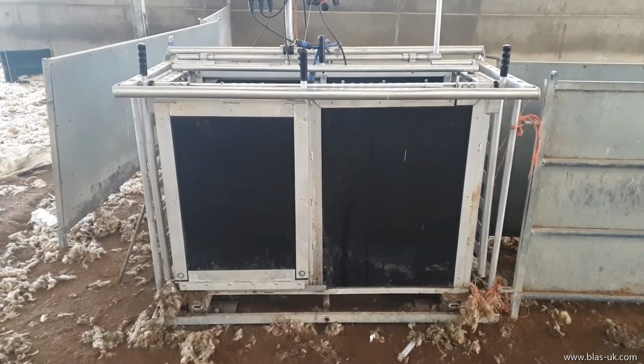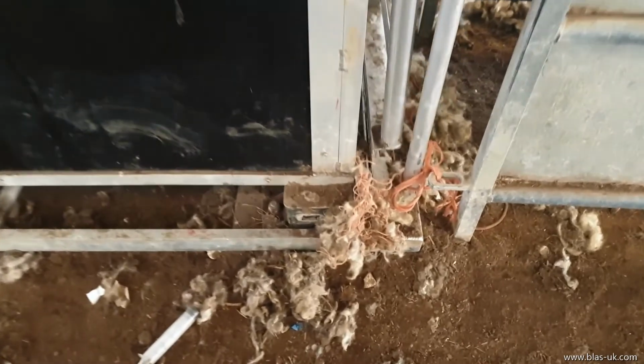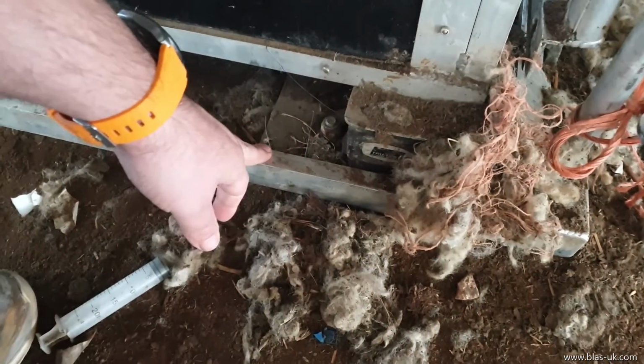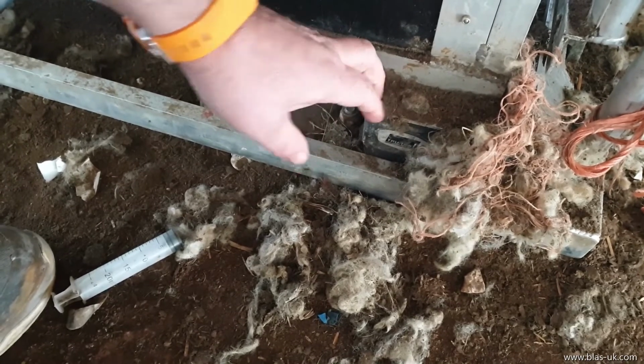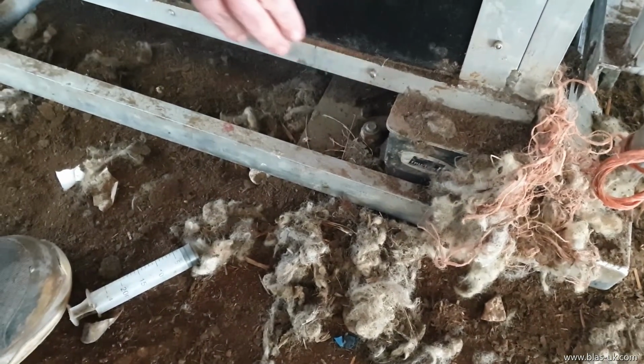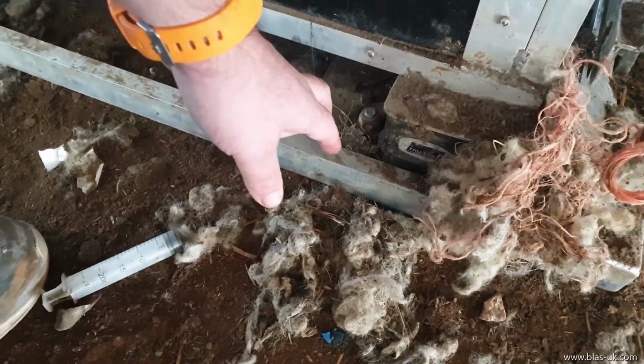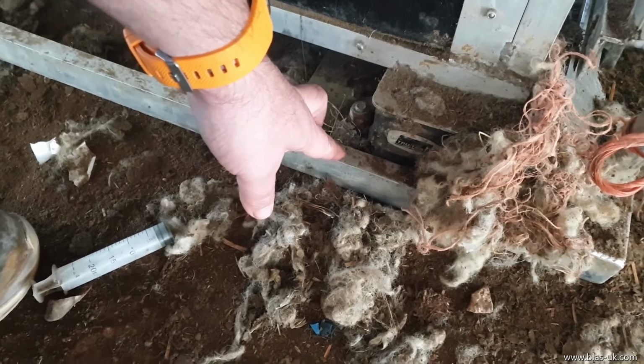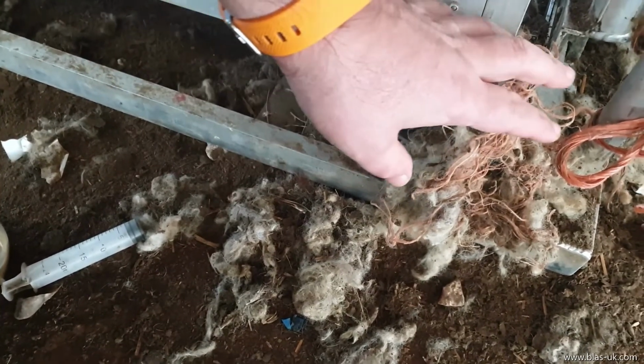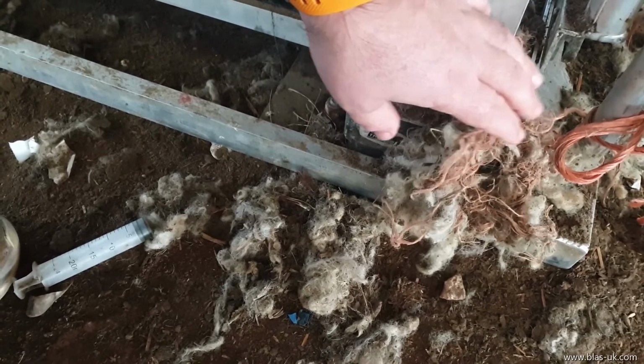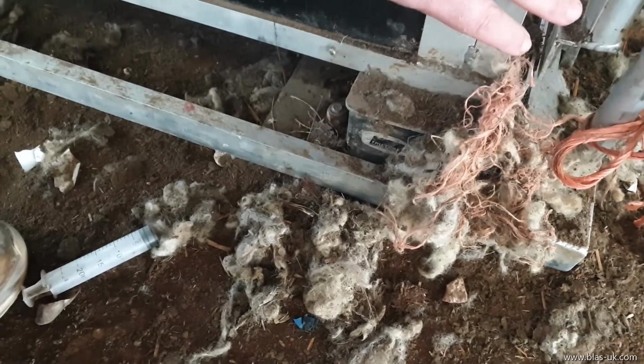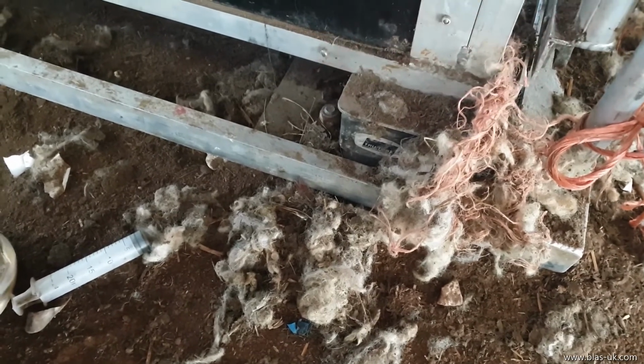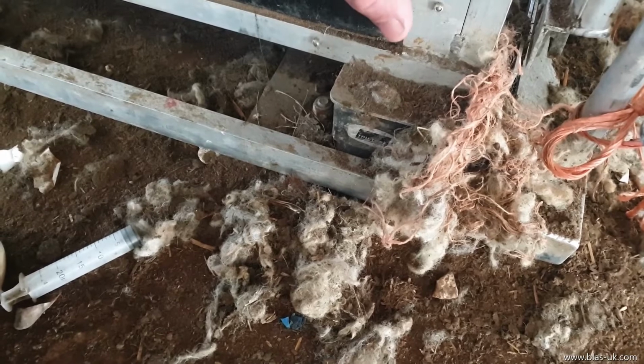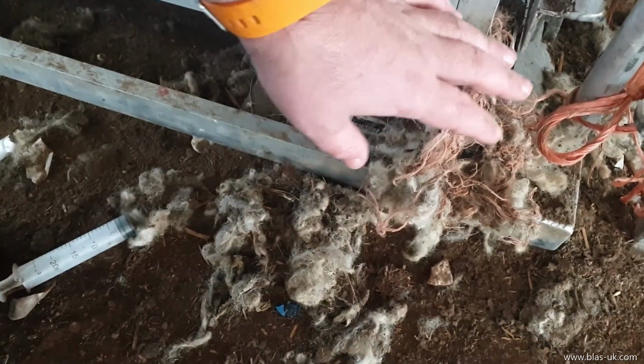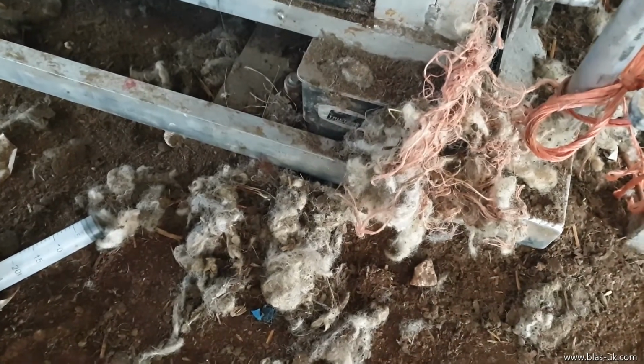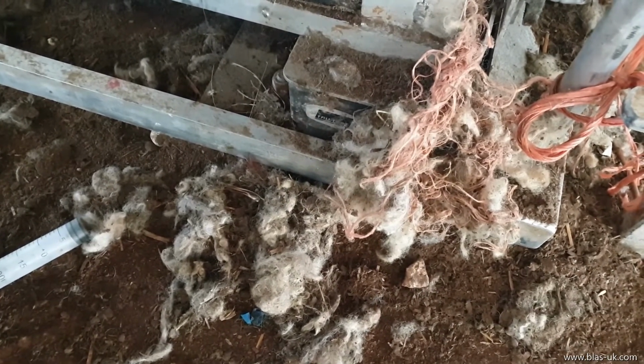Also, there's an isolation frame on most weigh crates, separating the weigh cell or the weighing system, the weigh crate, which is bolted to the weigh cell, which is then bolted to the isolation frame. If we get debris, muck, wool, string, etc. between the weigh crate and the isolation frame, lowering the ability for the load cell to push down, because this is given a resistance, this will lower your capabilities of getting an accurate weight. It will still give you a weight, but it'll be less accurate.